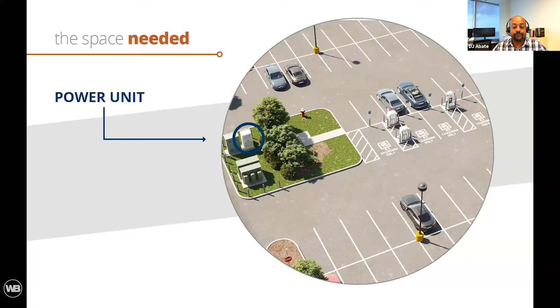Ideally, you'd want these installed in front of a parking spot, in between parking spots, so 2 cars can share it. But that's only if the parking space is deep enough or there's room in front of the spot, which isn't the case in most parking lots. So what we'd do is stripe the parking area and locate chargers in between parking spaces, which means some spaces would be lost. In this project, we lost 2 parking spaces to accommodate the 3 chargers, and we were able to provide 1 ADA-compliant charging station. So the amount of space needed is very site-specific, depending on the number of chargers installed and the actual physical conditions of the site.